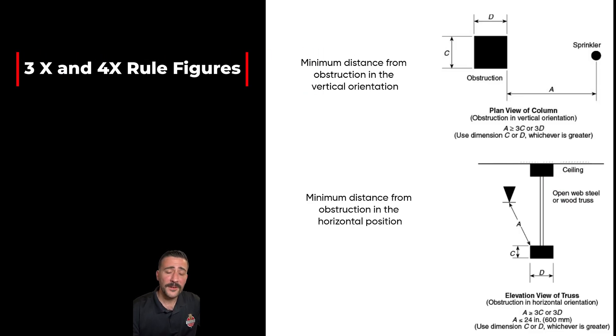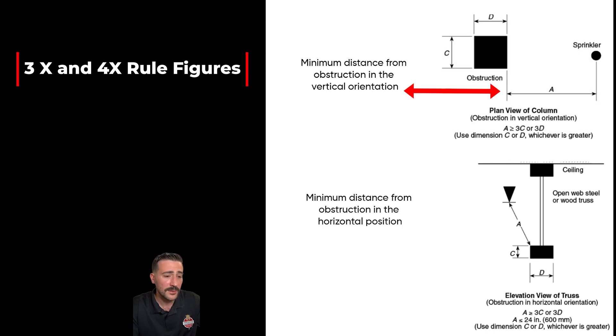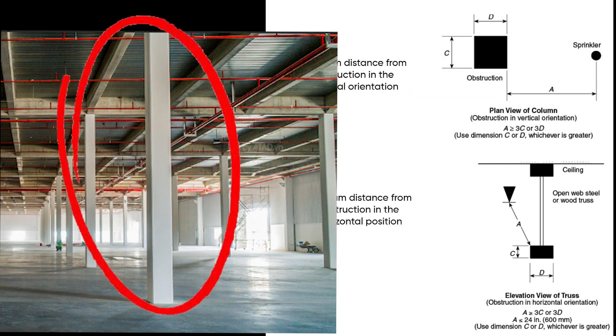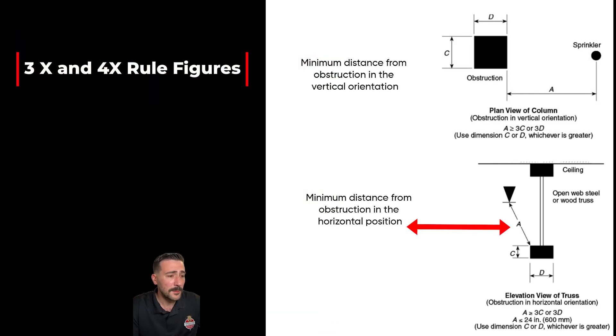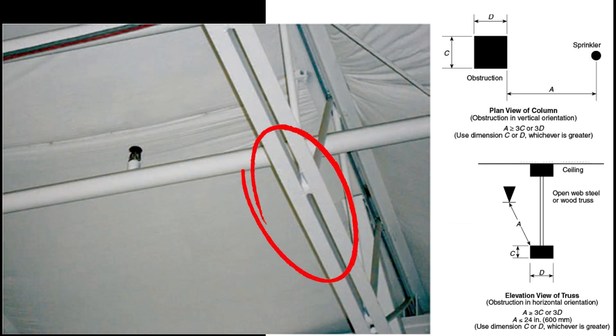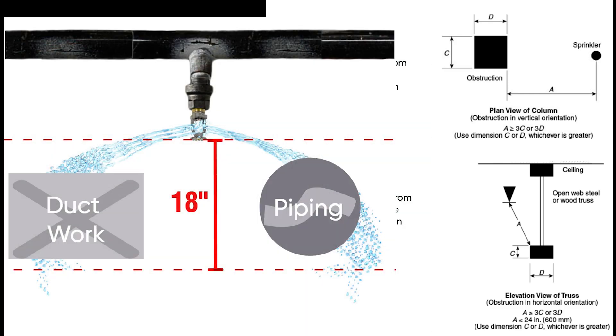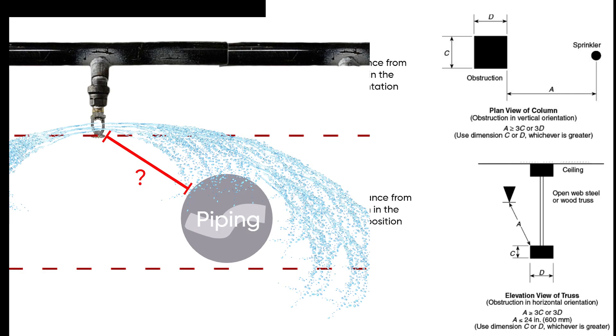Here are the figures for the three and the four times rule. At the top you can see the minimum distance from obstructions in the vertical orientation — for example, a column. At the bottom you can see the minimum distance from obstructions in the horizontal position; NFPA uses an open web truss as their example. Other examples of obstructions in the horizontal position could be piping, conduit, ductwork, and lighting. The three and the four times rule gives us the distance we need to be from the obstruction when our head is within the discharge pattern development zone.